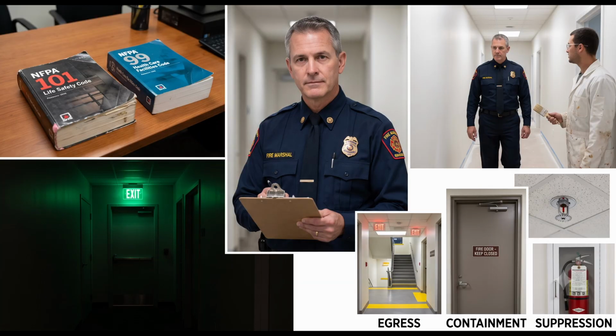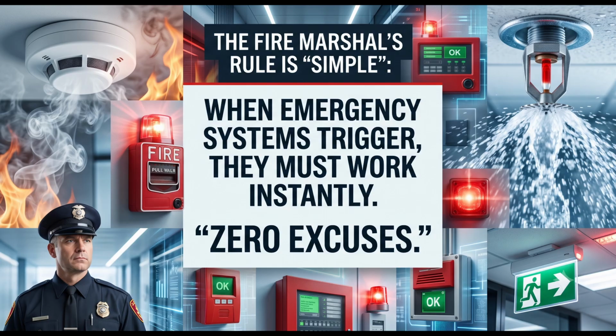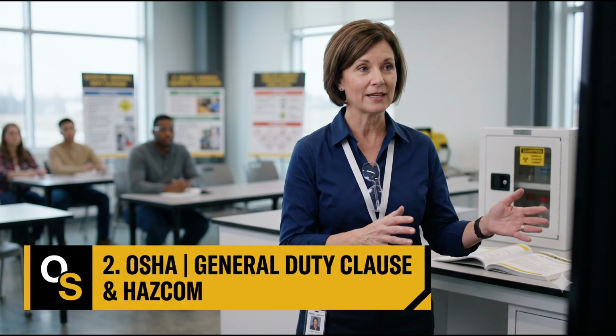Their Bibles are NFPA 101, Life Safety Code, and NFPA 99, Healthcare Facilities Code from the National Fire Protection Association. They couldn't care less if the paint color looks nice, but if a hallway light leaves an exit route in the dark, you've got a problem. At their core, they care about 3 non-negotiables: egress, fire containment, and fire suppression systems. The Fire Marshal's rule is simple. When emergency systems trigger, they must work instantly. 0 excuses. Next is Occupational Safety and Health Administration, OSHA.